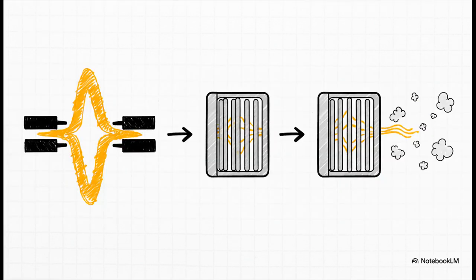But here's a question. What happens when these contacts snap open under that much power? The electricity doesn't just stop. It can form a super dangerous, high-temperature arc, basically a bolt of lightning inside the breaker. To deal with that, the MCCB shoves that arc into a special chamber called an arc chute, which splits it, cools it, and safely snuffs it out.